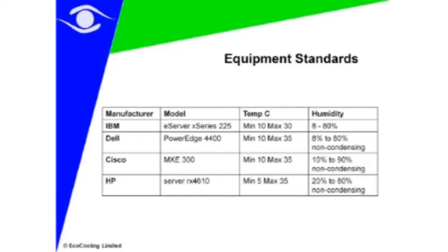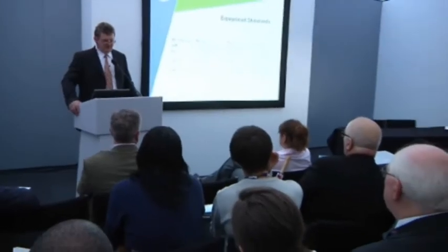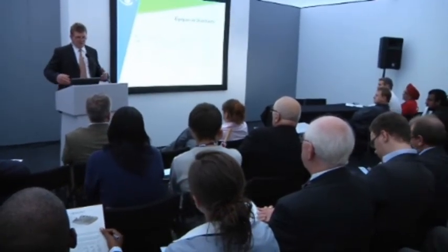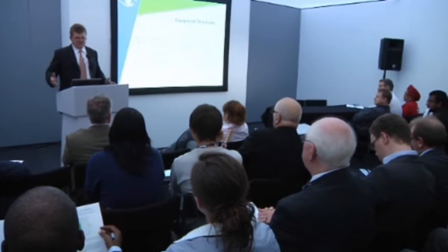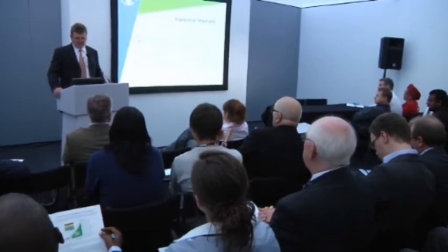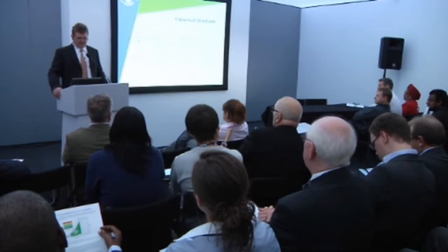You would expect IBM to have some fairly rigorous standards. Take a standard server from them and suddenly you see that the temperature spec is 10 to 30 degrees centigrade, with relative humidities of 8 to 80%. When people look at their equipment, most of them have never been given the environmental operating specifications, and that's a surprise to most people.